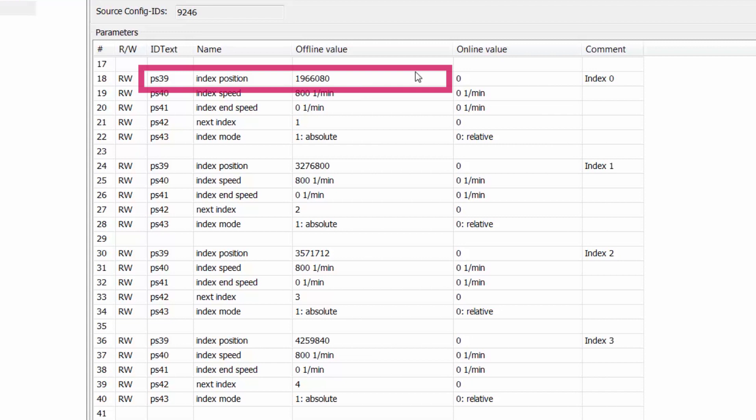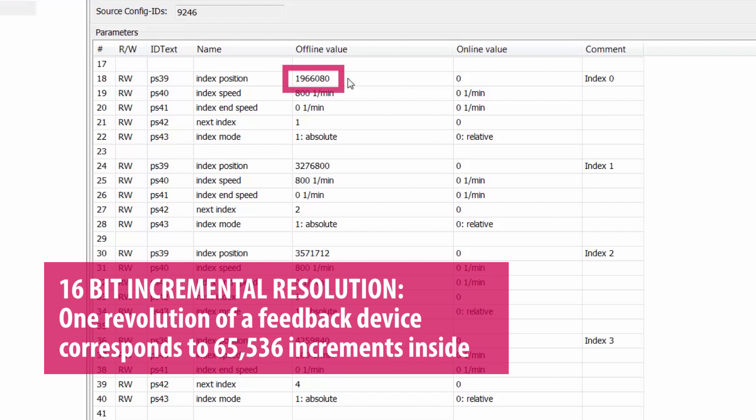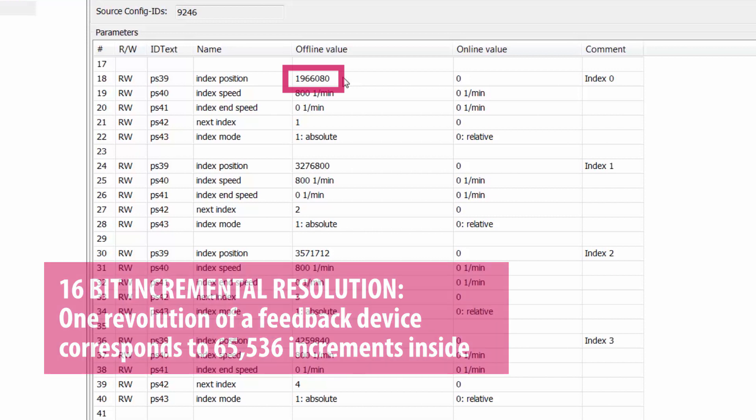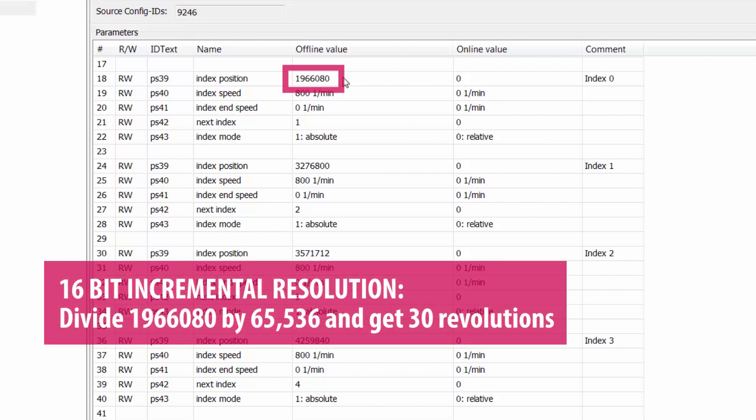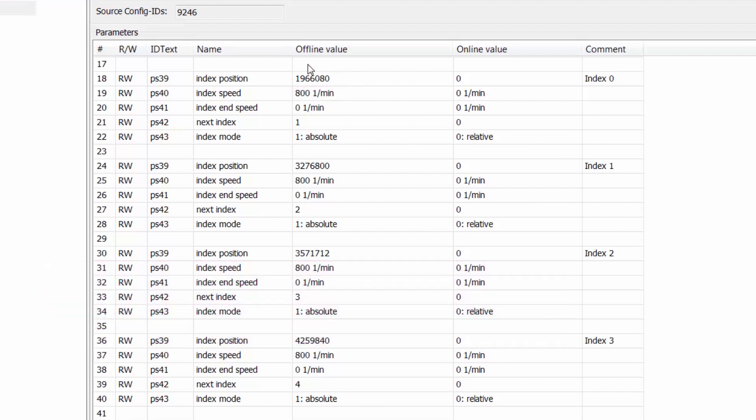So looking at index 0 the first parameter we see is PS39 index position. The value of this index position may seem rather large and a little bit confusing to you at first however the S6 drive actually utilizes a 16-bit incremental resolution for every feedback device that is connected to the drive. What that means is for any feedback device connected to the drive one revolution of that device corresponds to 65,536 increments inside the drive software. So this large value if you divide that by 65,536 equates to 30 revolutions so this is just moving 30 revolutions from its starting point or zero position.